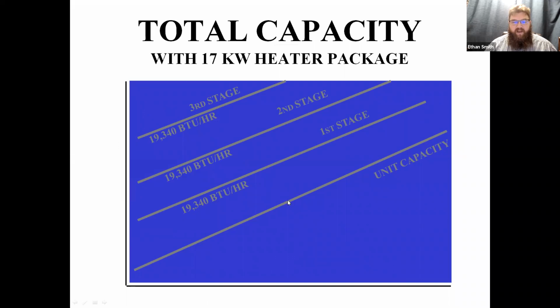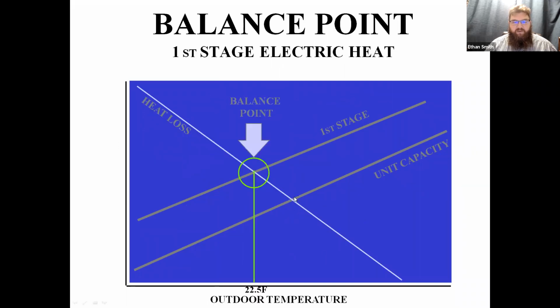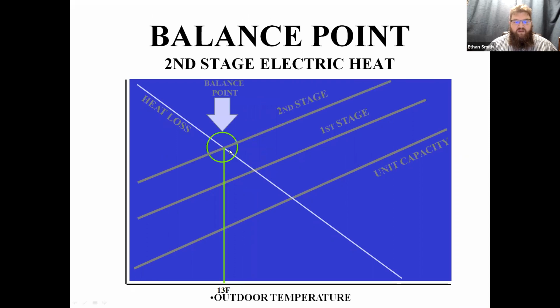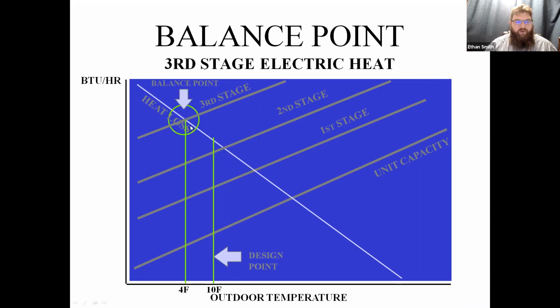So I know my unit capacity is here. I can put my first balance point at 22 degrees. So I know when the outdoor temperature is at 22, I'm going to need auxiliary heat because I'm below my system capacity balance point. So at 22 degrees, I may bring in a first stage of electric heat. At 13 degrees, I may bring in a second stage of electric heat. And then at 4 degrees, I may bring in my third stage of electric heat.